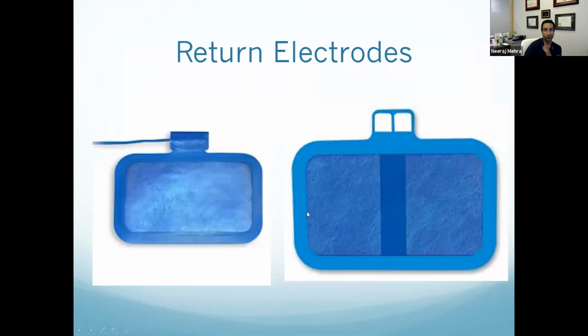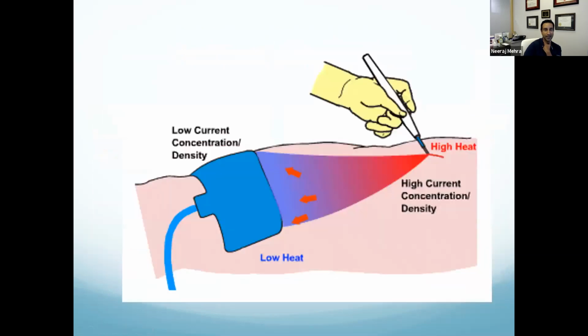Now, one of the safety features that you'll see in the return electrode is this. What your electrosurgical generator does is it says, I want the electrons going out to be the same amount coming back in. I want this circuit to be complete. So I want to sense that things are coming back. But it doesn't know what's happening at the tissue level.